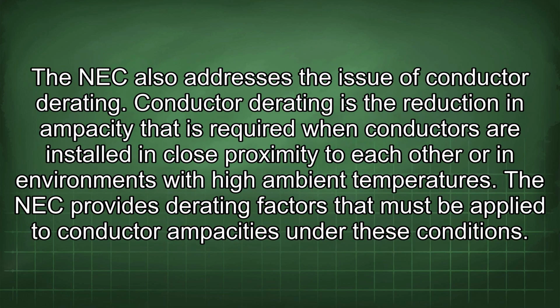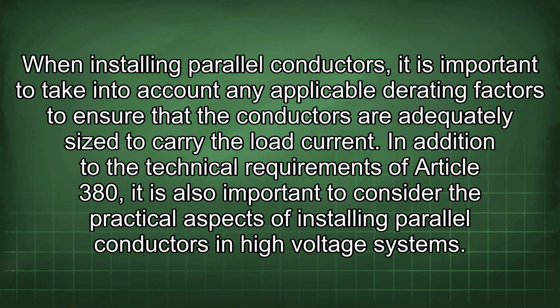The NEC also addresses the issue of conductor derating. Conductor derating is the reduction in ampacity that is required when conductors are installed in close proximity to each other or in environments with high ambient temperatures. The NEC provides derating factors that must be applied to conductor ampacities under these conditions. When installing parallel conductors, it is important to take into account any applicable derating factors to ensure that the conductors are adequately sized to carry the load current.